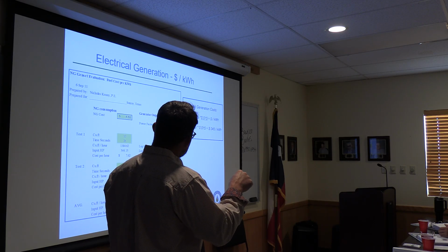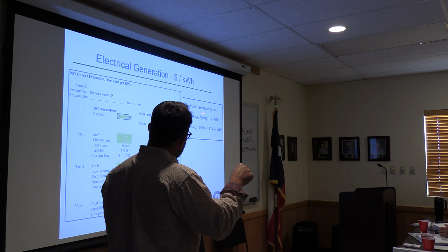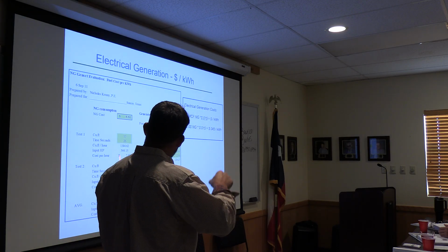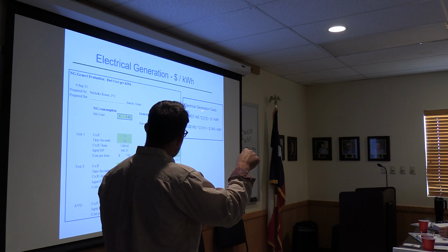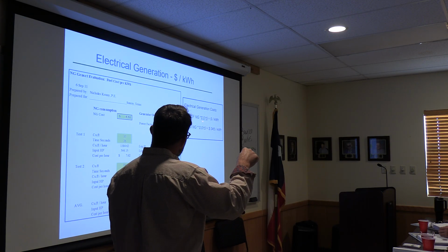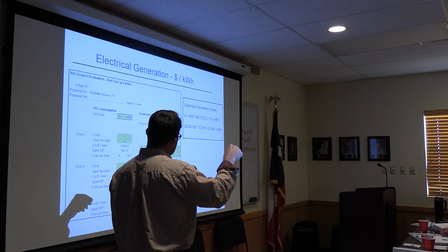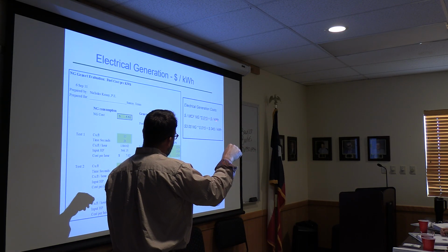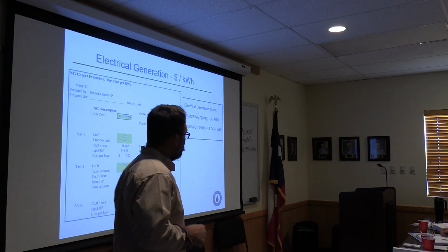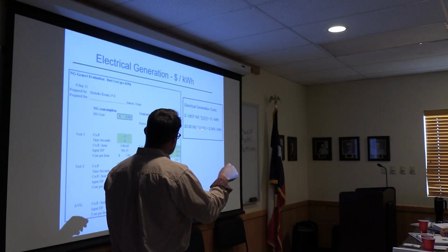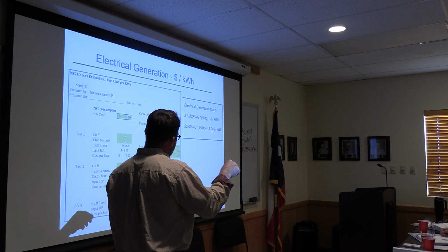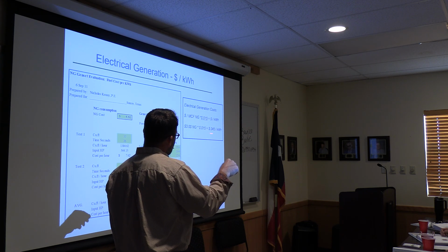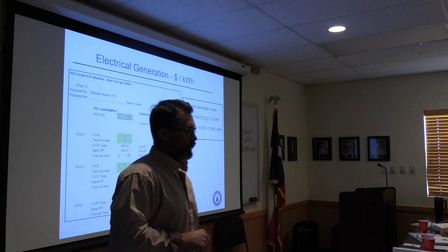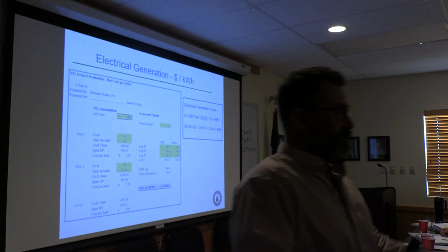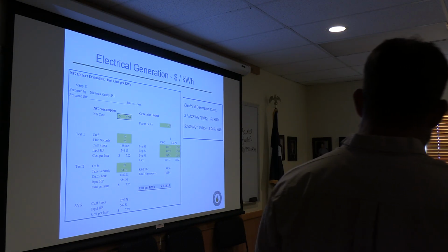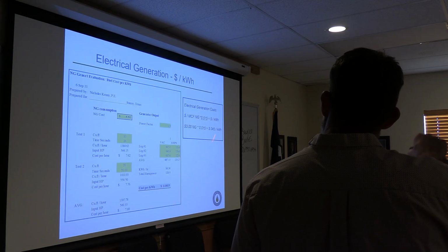You take your dollars per MCF of natural gas times this multiplication factor, which is basically the summary of all of these things we saw in the field, of 0.015 as a multiplier. That's going to give you the dollars per kilowatt hour you can produce electricity for. So in this case, if you've got $3 natural gas times 0.015, you can produce electricity for 4.5 cents per kilowatt hour. The reason I'm saying this is if you're going to compare to the grid, this is your shortcut to answer whether gen sets are even for you.